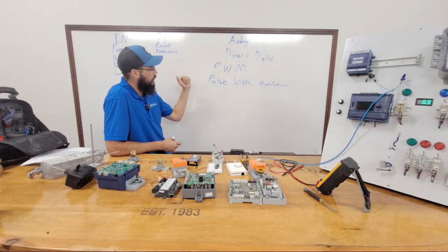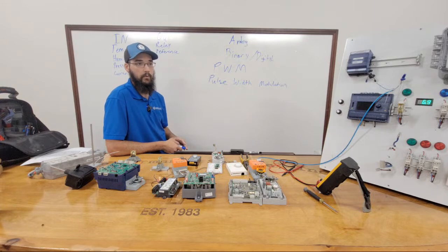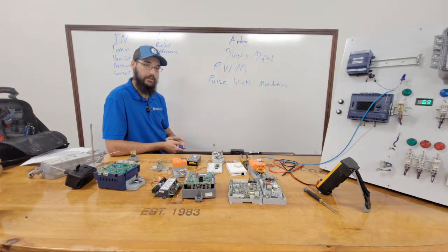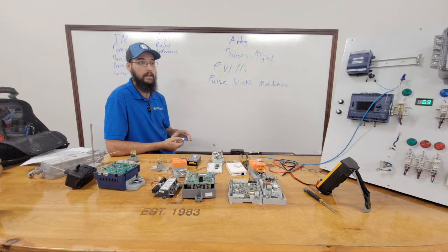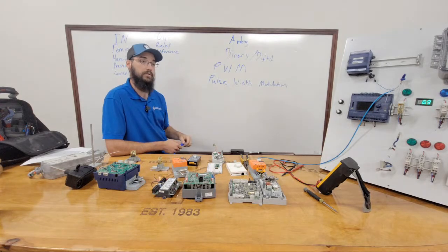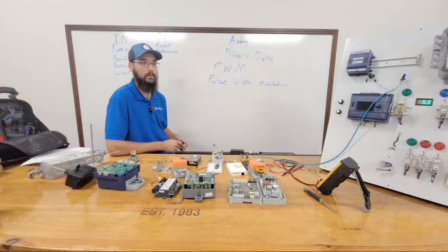Right? Ultimately, pulse width modulation is also entered into, say, mag bearing equipment. When you start talking anything mag bearing, we use PWM technology to create the control circuits and the magnetic fields we need in order to levitate those shafts and have magnetic bearing oilless systems. That is how we're accomplishing it.